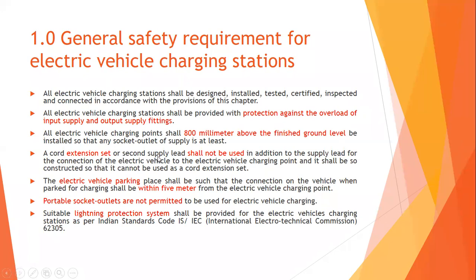A cord extension set or second supply lead shall not be used in addition to the supply lead for connection of electric vehicles to the charging point — extension sets at EV charging stations are prohibited. The electric vehicle parking place shall be such that the connection on the vehicle when parked for charging shall be within five meters from the electric vehicle charging point.